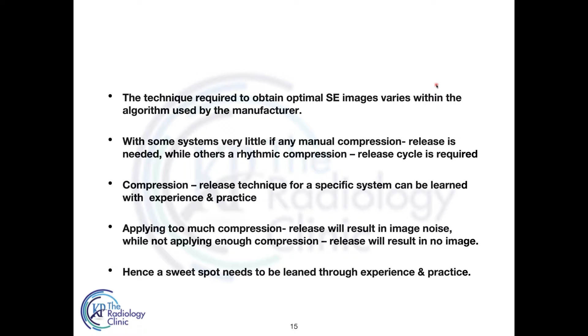Some vendors have a visual scale that helps to confirm the optimal compression release and the frequency that is applied. But a high quality factor alone does not guarantee optimal images. There are many other factors also. The main thing is that the lesion should appear similar in all frames of strain elastography. If not, then there is non-uniform displacement of the lesion during scanning, or an unacceptable pre-compression is being applied.